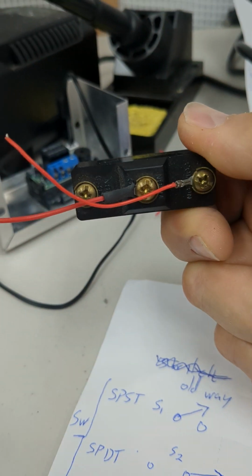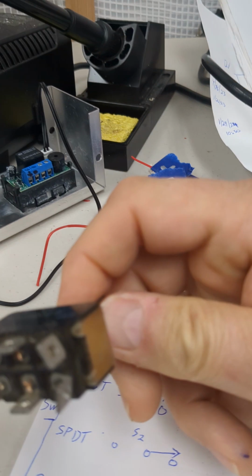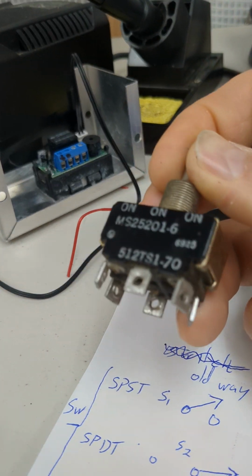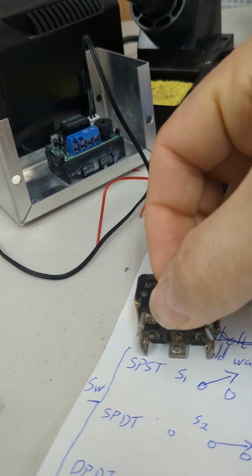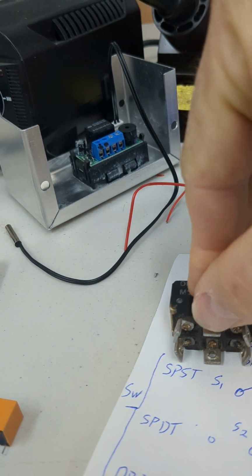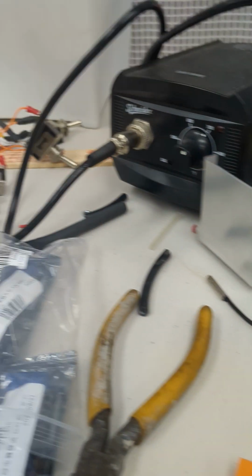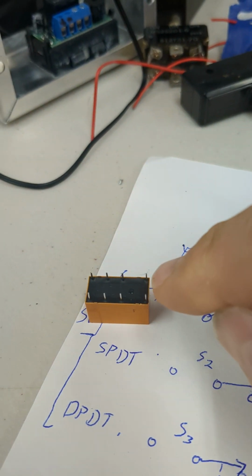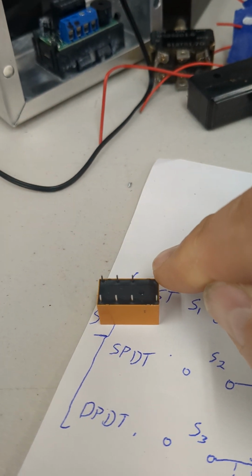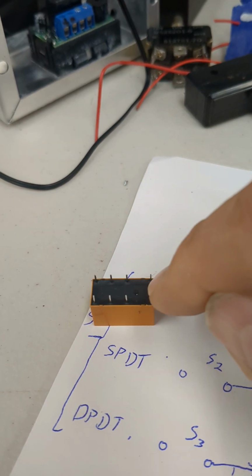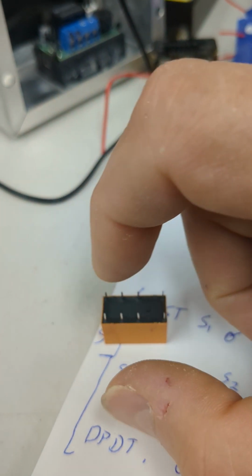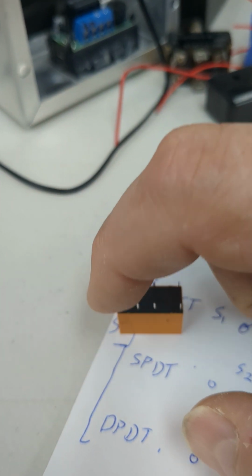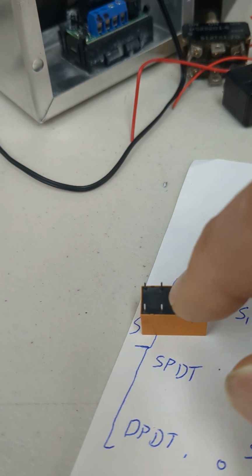This is a single pole, double throw. And then this switch is a double pole, double throw. On, it's momentary, but power goes to the middle, and then flip one way it goes here, flip the other way it goes here, and there are two individual poles. And here's a relay, and the relay is the same, but these two terminals here are the coil, and you put power to the coil and it flips the switch for you, and the power goes to the center, and then off goes to the normally closed contacts, and on it goes to the normally open contacts.